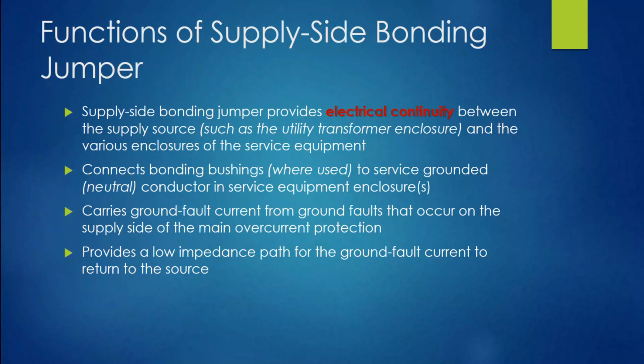All right, it does connect everything to earth because back at that transformer, that grounded conductor is connected to earth by a chain of ground rods as well. So, yes, it's not going to trip any overcurrent device that we deal with, but there is a fighting chance, and the code requires it all to be bonded together as well. So I wanted to give you that overall understanding before we dig into some of the language. That way you understand it better as we delve into it. So a supply side bonding jumper provides electrical continuity between the supply source, such as a utility transformer enclosure, and the various enclosures and raceways of the service equipment.